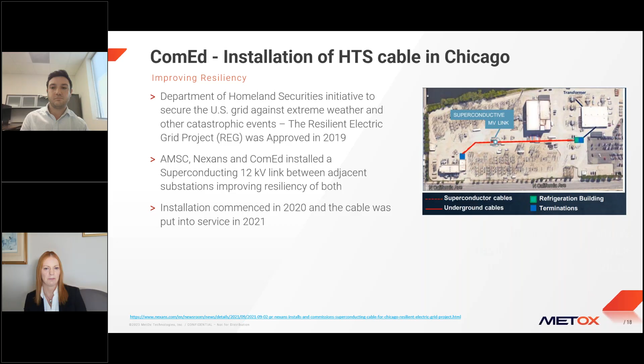Closer to home in the US, ComEd are probably the most recent installation of an HTS cable. This took place in Chicago in 2020 and 2021, a partnership between American Superconductors, Nexans, and ComEd. In this case, they were linking two adjacent substations with a superconducting, very high capacity cable, and effectively this link was going to provide a backup from one substation to the other. So in case of the loss of infeed to substation A, it could be supplied from substation B. This was considered a resilience project, sponsored by the Department of Homeland Security as an initiative in securing the US grid against extreme weather and catastrophic events. It was installed in 2020 and put into service in 2021.